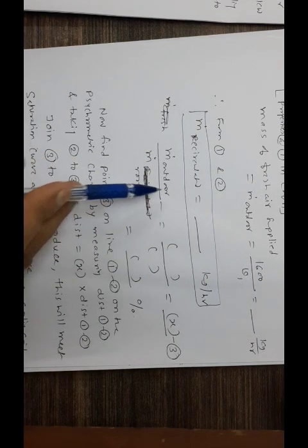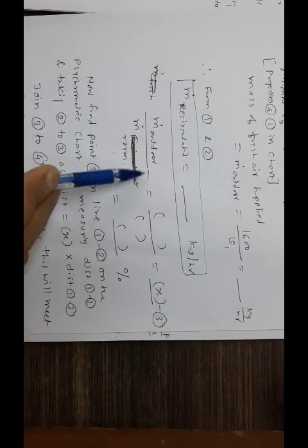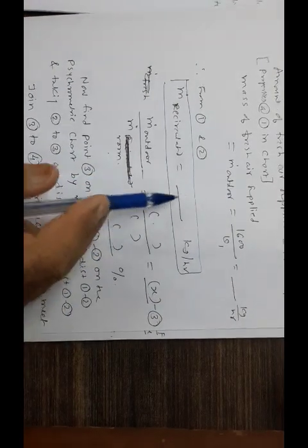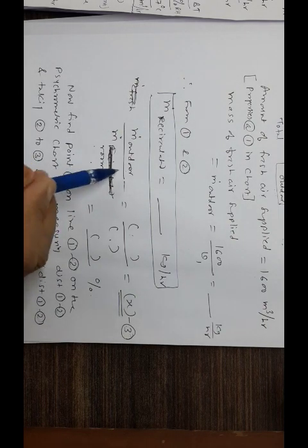Now we have to take a ratio of outdoor air, which is known to you, the mass of outdoor air, divided by the total mass supplied to the room. So outdoor air 1,600 is converted to some value here, and m dot room is what you have obtained from the earlier case. This ratio is what I called x. Why we are doing this is because we want to see how much part of the outdoor air is associated with the room air. That's what we are trying to look into.